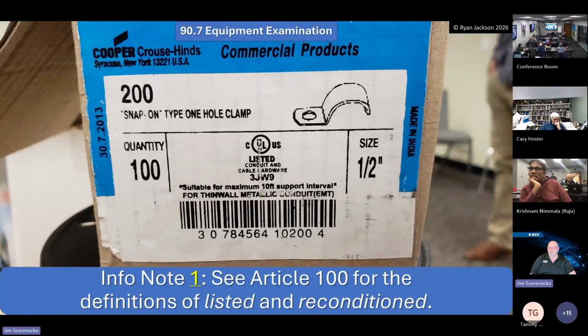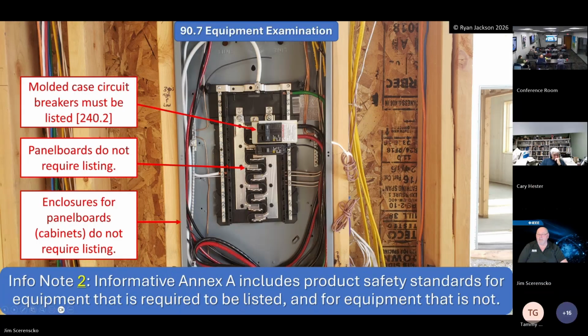And then, of course, note 1 for definitions for listed and reconditioned. Obviously, you're not going to recondition a strap, but we want to make sure that the straps are listed. The reason they put this in here is the listing does not have to be on each piece. If it's listed on the packaging, then it's all good to go. Also, again, we are allowed to look for modifications or damage. That is the extent. We get a lot of pushback from engineers about certain products that they're using and how they're being used. So we want to make sure that it's being used the way it was designed to be used.